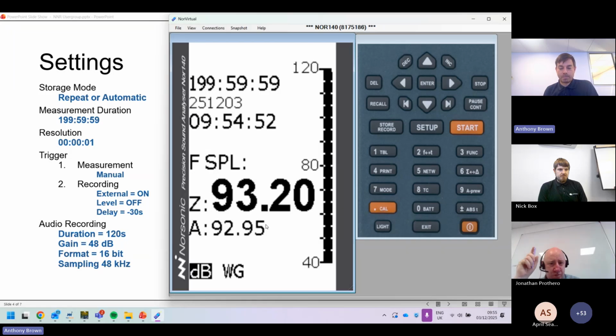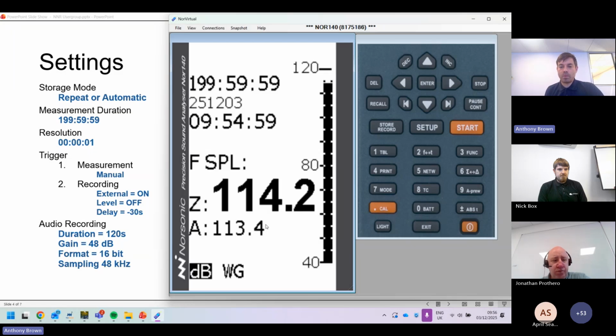And I'm just going to place my calibrator on the end of the microphone. I'm not going to change any settings, so I'm just going to place it on there. And you can see straight away that my microphone then starts reading 113.6. So it's a little bit off 114. So we should just adjust that just to make sure it is working.